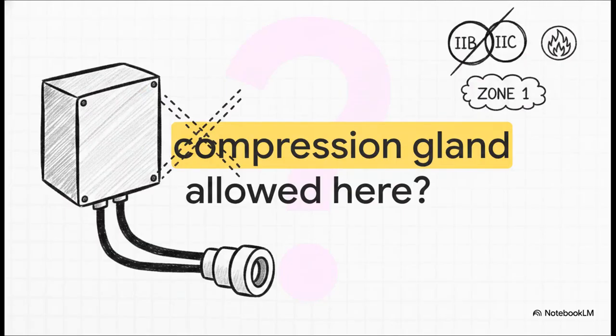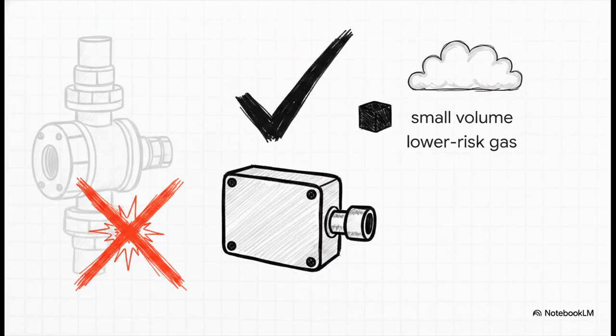Okay, quick pop quiz to see if we're on the same page. Let's say an Ex d junction box has an internal volume of 1.5 cubic decimeters. It's in Group 2B gas service, and it's located in Zone 1. Based on the rules we just went over, is a standard compression gland allowed? What do you think? The answer is yes.